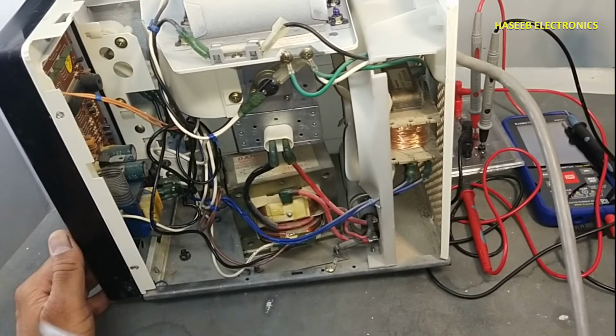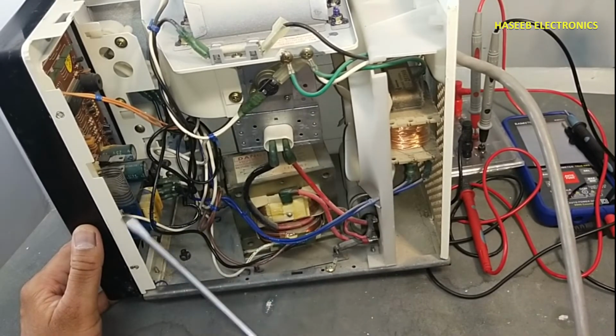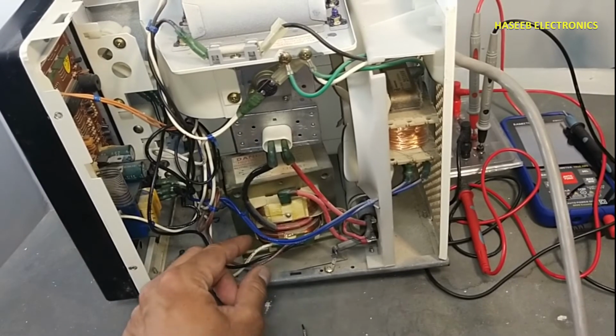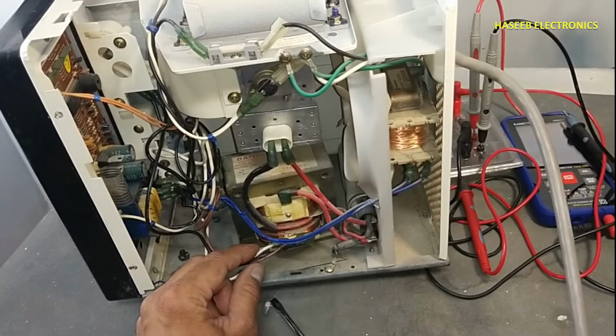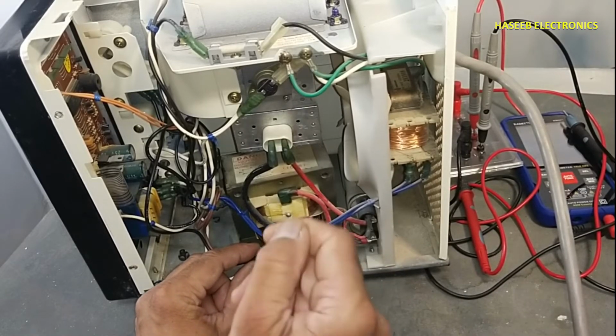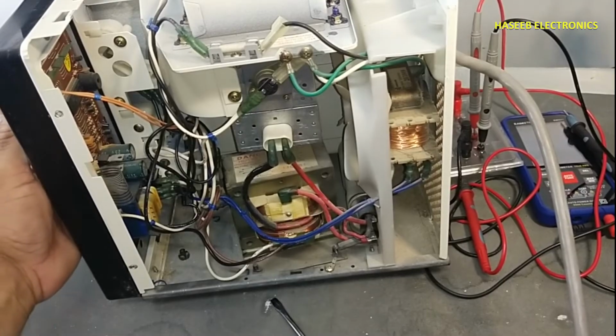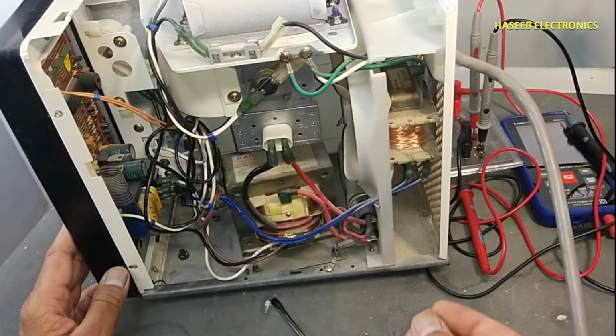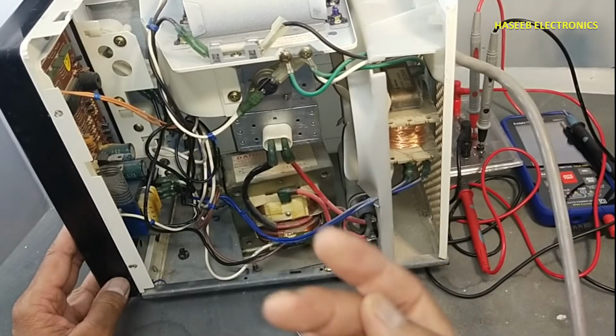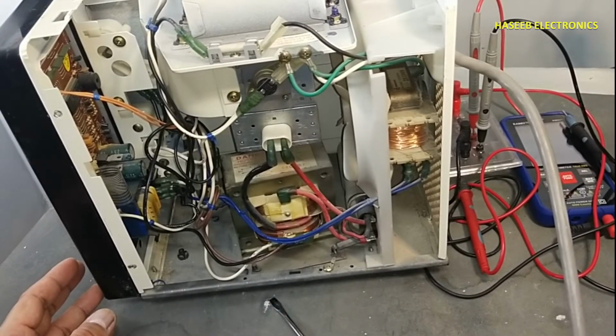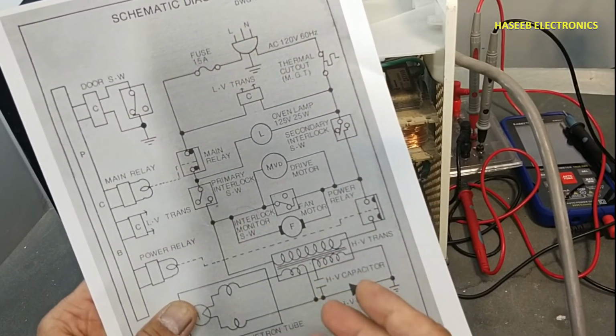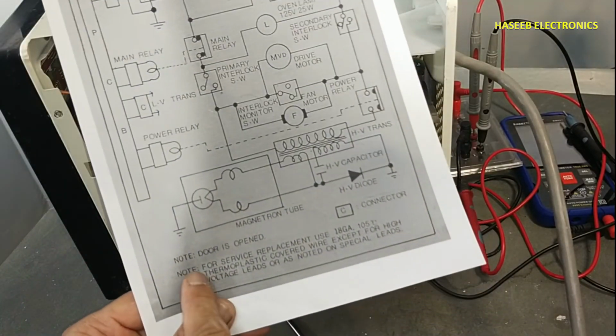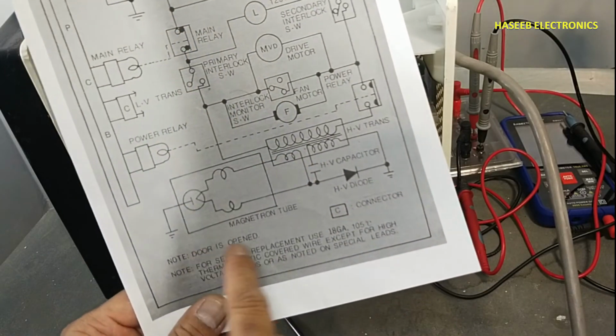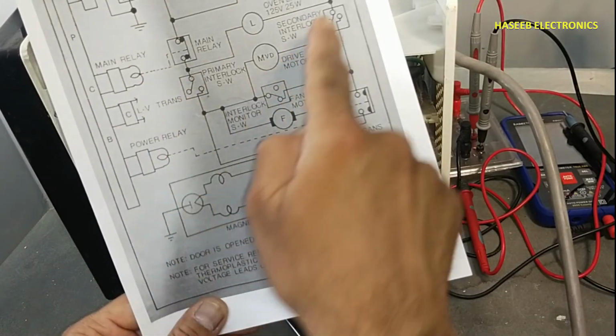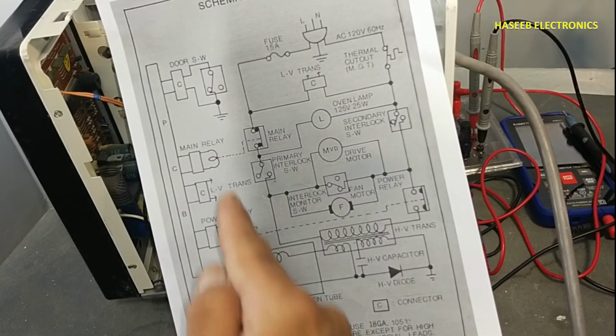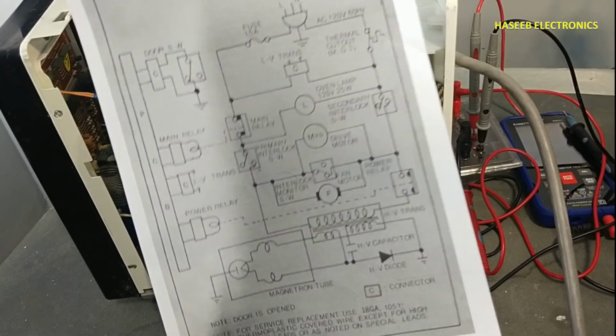If these switches are misaligned or a switch is malfunctioning, it will not provide voltage at these 2 points. The same way we tested the voltage, we can remove these connectors and test the voltage. Just close the door, select the timer, apply voltage, and the multimeter will show the voltage. If it is not showing the voltage, we can follow the diagram. In the diagram there is a key noted for the opened position, showing the position of the switch when the door is opened. So we can follow those guidelines to see how the circuit is working.